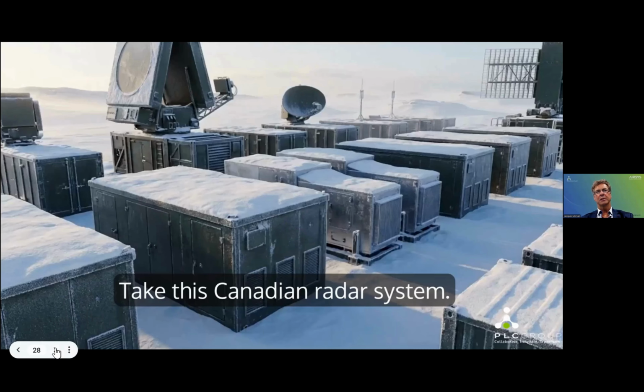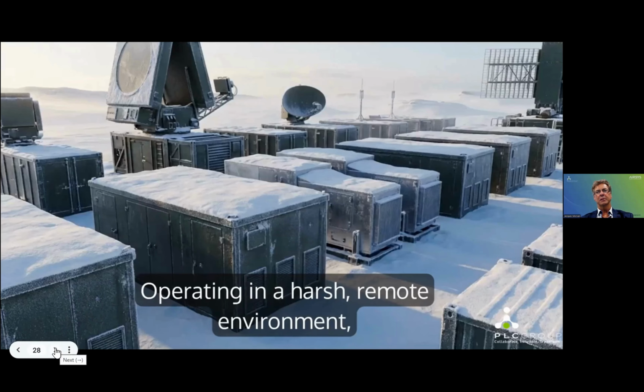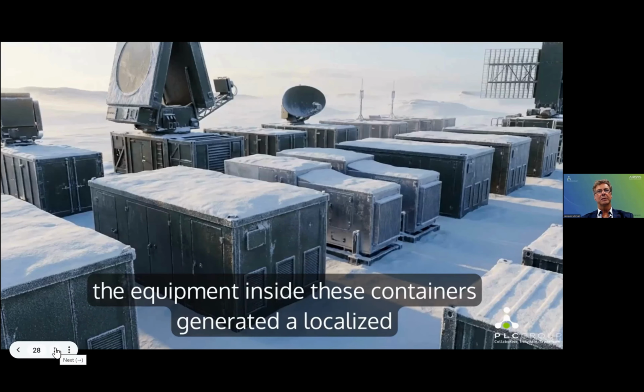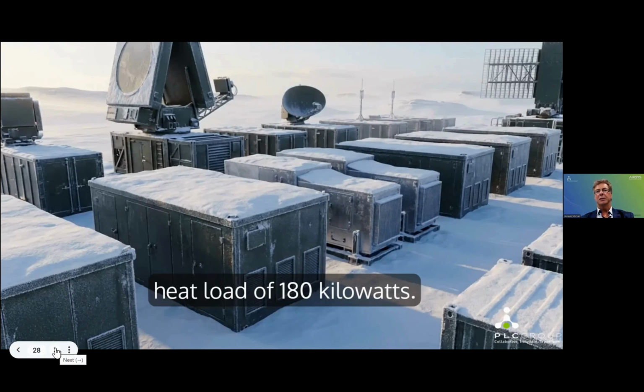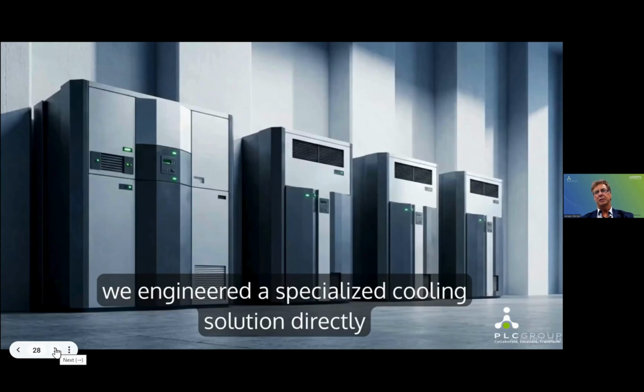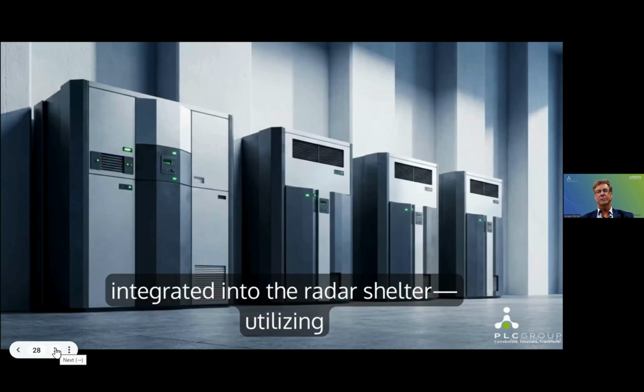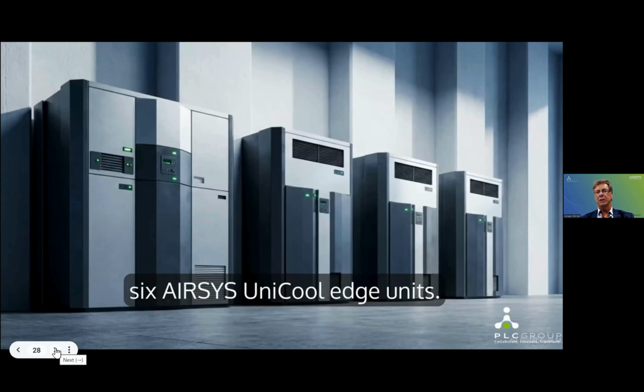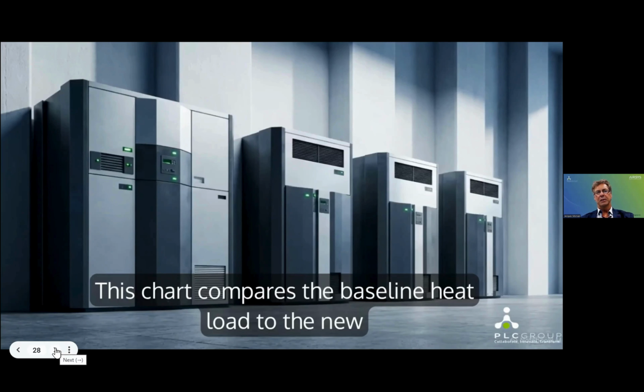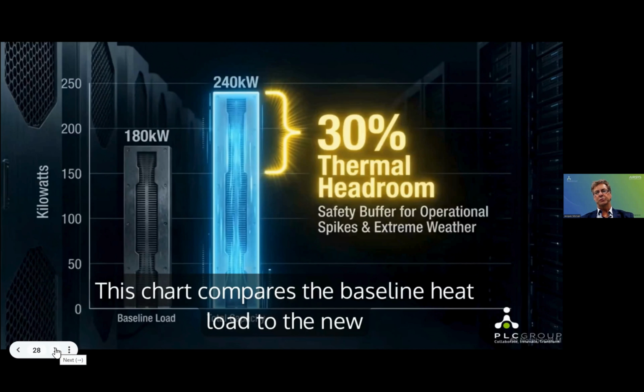Take this Canadian radar system. Operating in a harsh, remote environment, the equipment inside these containers generated a localized heat load of 180 kilowatts. To counter this, we engineered a specialized cooling solution directly integrated into the radar shelter, utilizing 6 AIRSYS UniCool Edge units. This chart compares the baseline heat load to the new system's output.